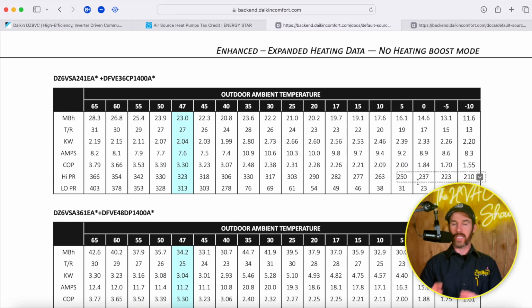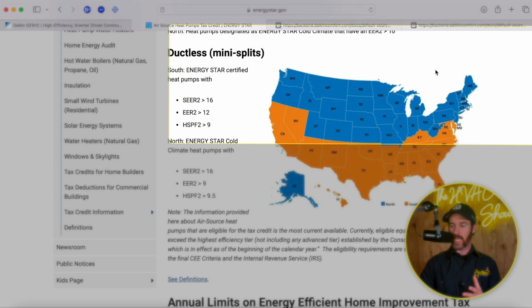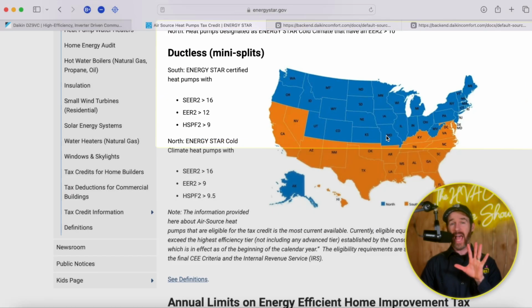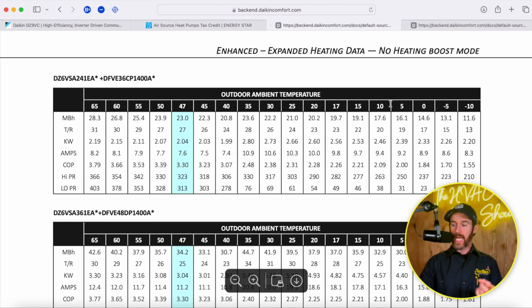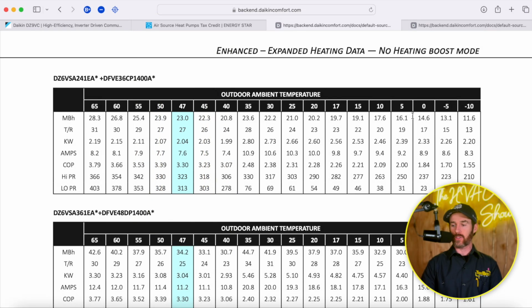The COP is 2. Now, the reason these numbers are important is that in order for a system to qualify for this heat pump tax credit in these northern blue states that I just showed you on this chart, it has to have a COP of 1.75 at 5 degrees Fahrenheit, and it has to maintain at least 70% capacity of its 47 degree temperature capacity. And so the system meets those parameters, and that's why it qualifies as a cold climate heat pump.